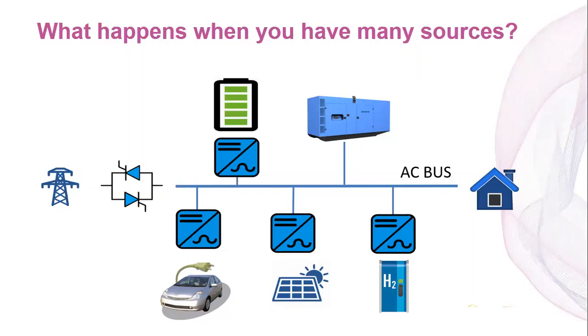In the case of a DC microgrid, I think there is a big advantage in the fact that there is an inverter breaking the direct connection between the AC grid and the DC bus. That means any disturbance on the AC bus stops at this inverter, and you are always running some type of voltage control on the DC bus. So the transfer from on-grid to off-grid is possible to make much smoother in DC microgrids.